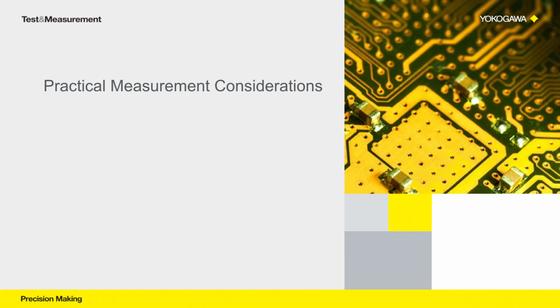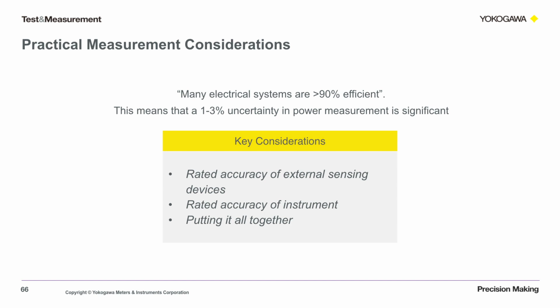When we decide on a measurement system, we need to make a few considerations to determine the best instrument. Given efficiency is becoming more and more significant in our measurements, we need to make sure the instrument and all of the measurements have better accuracy than what we're trying to measure. Putting these all together and adding all the sources of error are important before we start probing onto our devices or wiring anything.